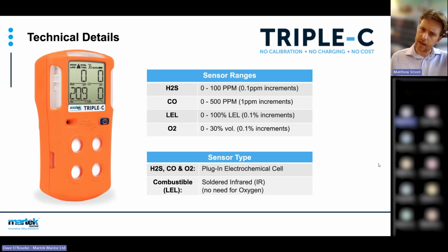The one to highlight is the flammable sensor, which is the infrared sensor I mentioned, with the other three being more standard electrochemical cell type sensors. The flammable sensor is only up to 100% LEL, around 5% methane.